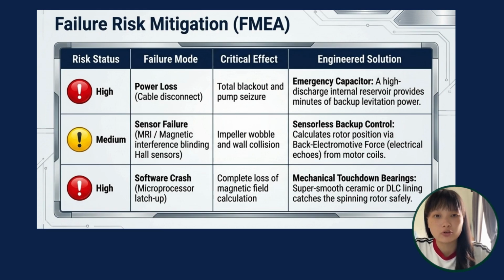This controller might send the wrong signals to the maglev, causing the impeller to wobble violently or hit the housing. Therefore, we need a sensorless control logic. Program a sensorless backup mode into the software. This allows the computer to guess the impeller's position by looking at the electrical echoes coming from the motor coils. If the primary sensor fails, the pump automatically switches to this backup software logic to keep the impeller centered.